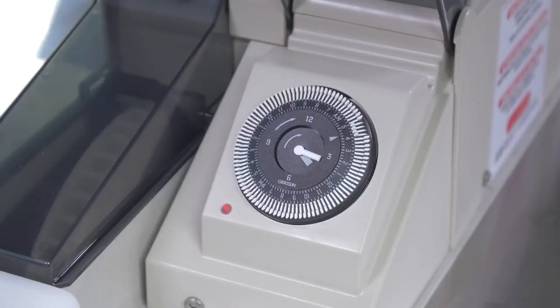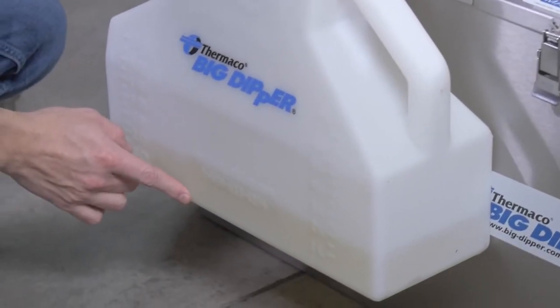To confirm that your Big Dipper is skimming correctly, allow the unit to run at the current setting for a few days. After a skim cycle, check the grease collector and observe the amount of water in grease.